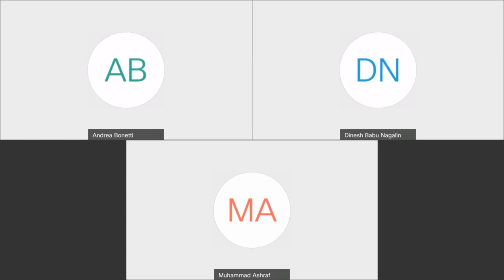As I said, is the IEDScout the full picture, simulating the physical relay? No. As I said, the IEDScout is simulating, but it's not the only one. There are many other tools that can do that. As I said, ITT 600 and SICAM PAS can do that since many years. They simulate the data model of the device. They don't simulate the protection algorithm in the device, because the 61850 does not standardize the protection algorithm.